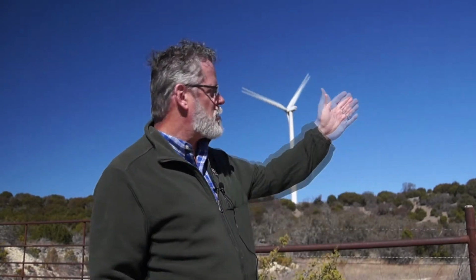The gearbox turns the shaft that goes into the generator, and the generator actually generates the electricity. That electricity comes down the tower to a pad mount transformer that steps up the voltage a little bit, and then that electricity goes via underground collection to a central point where a substation is, and at that substation they step up the voltage again to match the transmission line they're going to be tying into.